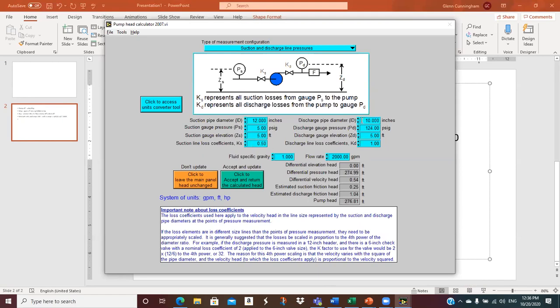And then on the discharge side, we have a discharge pipe diameter. Notice it's common, not always, but common, to have that discharge pipe a little bit smaller than the suction pipe. That's to minimize the pressure reduction on the suction side of the pump so that we don't get into a cavitation situation. We have a discharge gauge reading 124. Here we have a discharge gauge elevation. Right now it defaults to 5 feet on both sides, but you can change that. Your discharge line loss coefficients would be K sub D, which would be 1. We put in a specific gravity and a flow rate, and bingo, this calculates my pump head. That's the head that I would be generating on that pump curve.